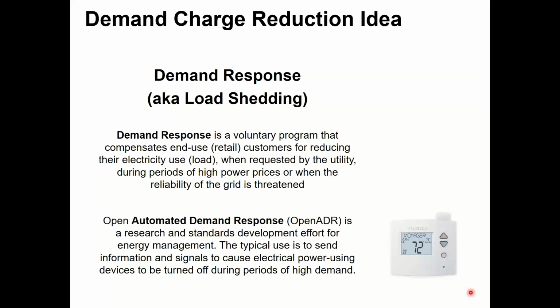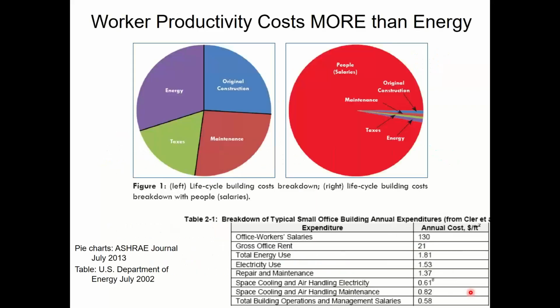So obviously I don't do that because 75 won't work for my customers. They won't be comfortable, or my clients or my tenants, or however you want to look at it. So I don't do that. So if I do it when the utility asks, it's going to lead people to be disgruntled. And when they're disgruntled, they walk around and complain about it, and they stand at the water cooler and complain about it, and they're just not very productive people at that point. So I'm not a huge fan of doing it this way. There's a lot of other ways to do it. It also reduces my ability to dehumidify, and it could cause some short cycling of my equipment if it's not set up correctly. Usually it's set up correctly, so no big deal, but it does hurt my dehumidification ability as well.